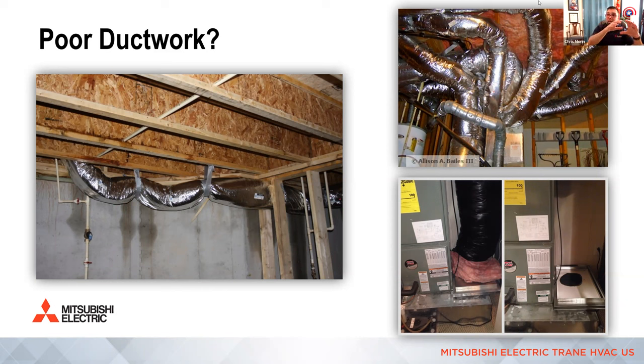If it's going to be a long trunk and you're going to take stuff tapered off the sides, maybe two or three runs would be okay with an SEZ with that size. I know it's very close to the aspect ratio. And that's why I was saying before, low static air handlers have a different process, and some things we ignore in order to make it work compared to mid or high static air handlers.